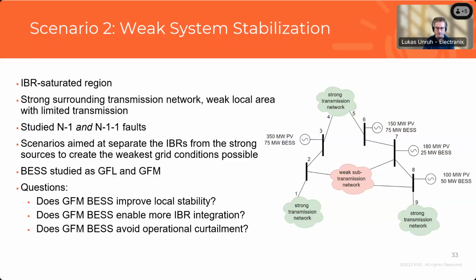And for those grid forming batteries, we used a similar modeling approach. Some of them were just a single OEM, some of them were a mix. And it's important to note that we didn't change any of the settings for these grid forming batteries. So they weren't necessarily tuned specifically for this weak system. They were the same settings as in the strong system.